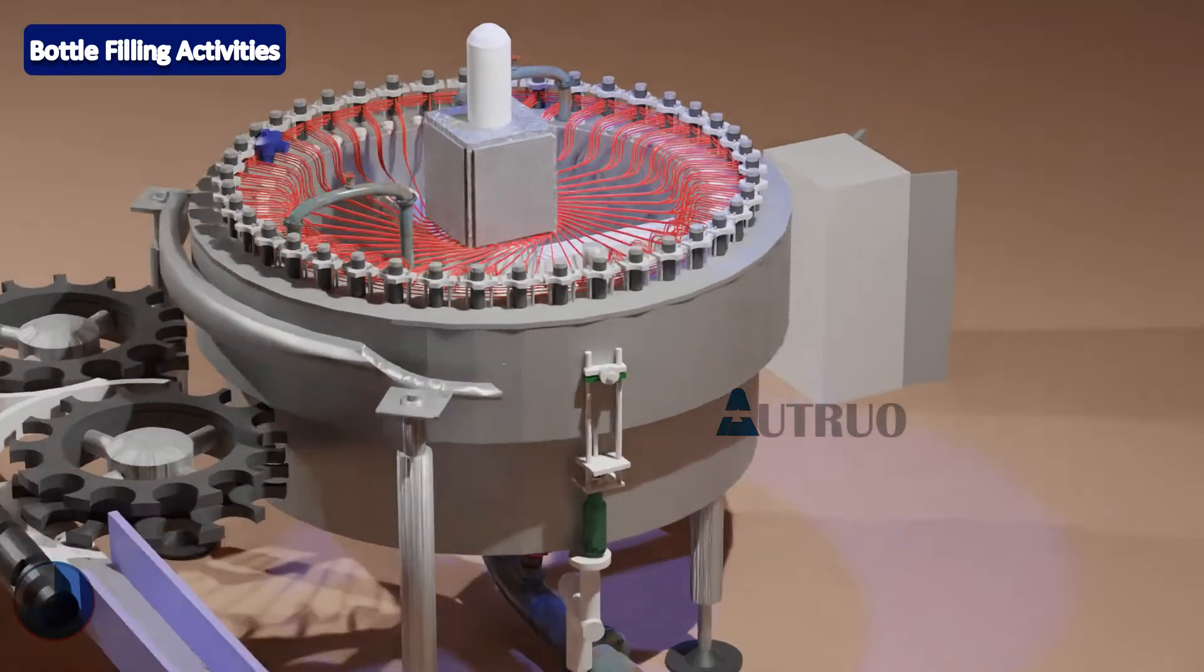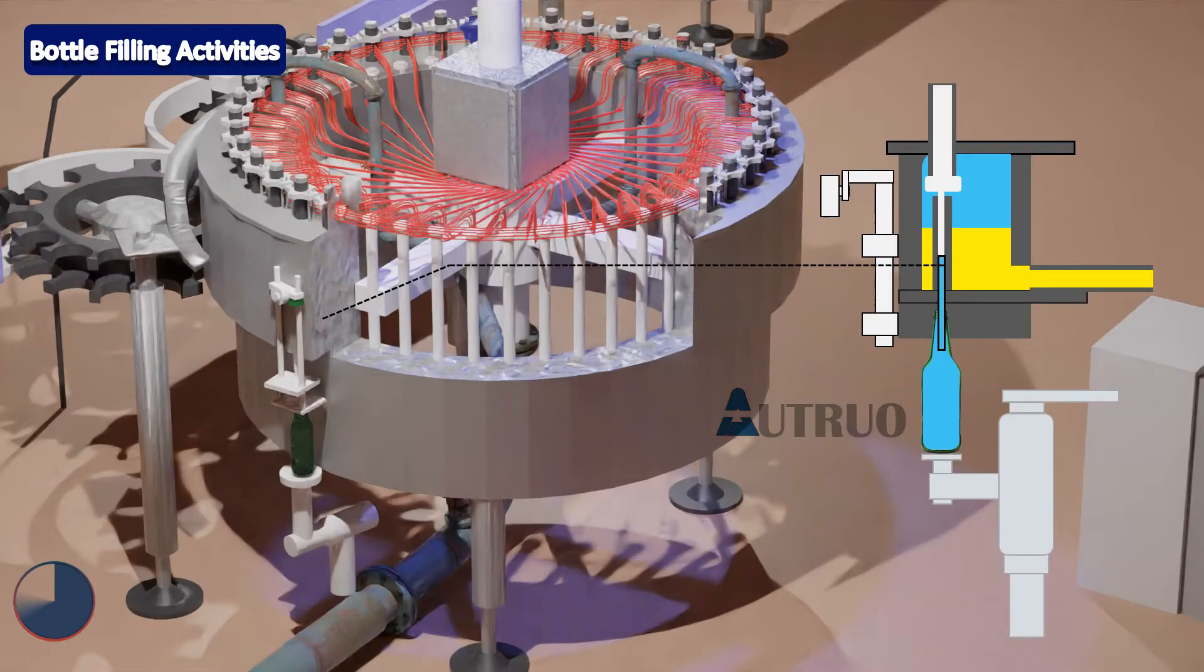When the filler rotation is from 5 degrees to 10 degrees, the PLC will use compressed air to activate the CO2 valves. This will allow the bottle to be pressurized with CO2.